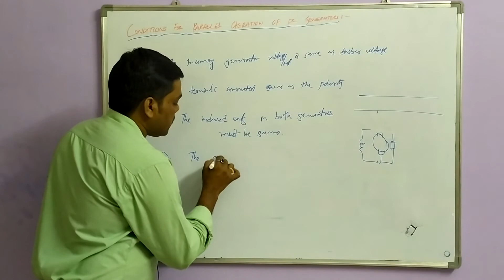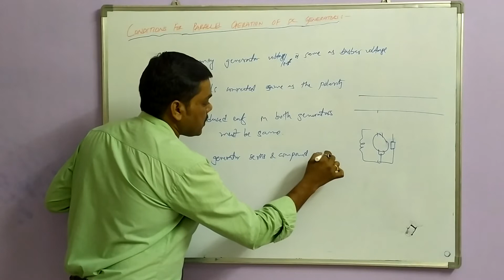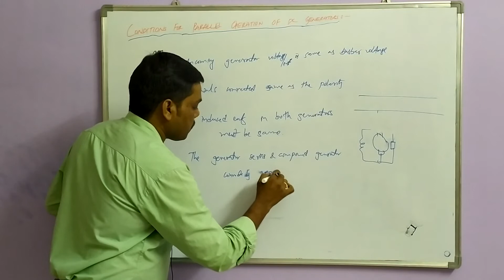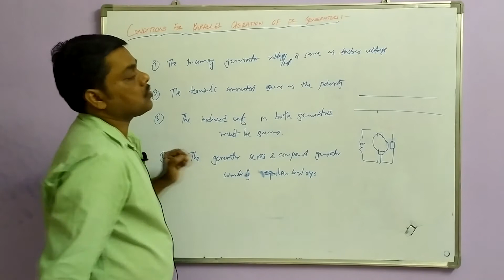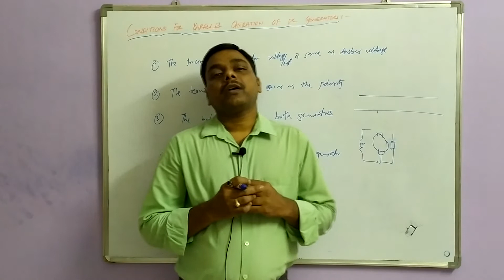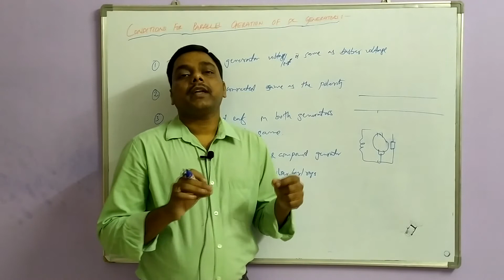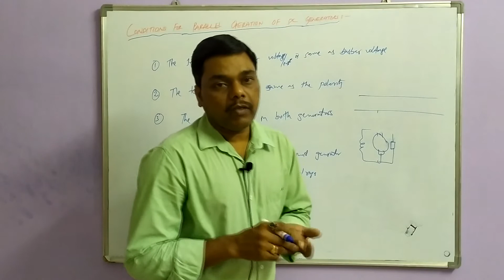Next, the fourth and most important one: series and compound generators must be connected by equalizer bars or rings. In a shunt generator, the shunt winding and load supply, but when you connect series generators and compound generators in parallel, the load sharing depends upon their internal voltage drop. So you have to balance both generators. You should connect the equalizer bar, which we call equalizer rings, in those generators so that they can share the load equally. If the load is shared equally by both generators, it will be a perfect parallel operation. Continuity and stability will increase.